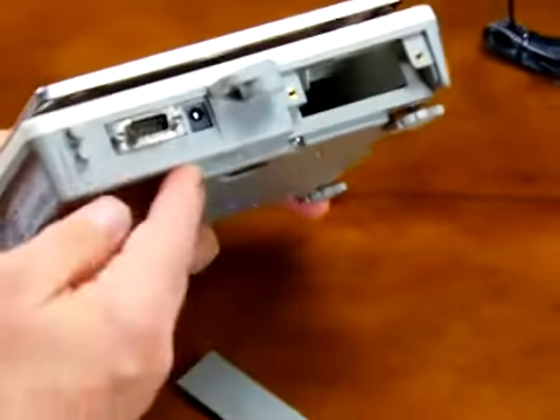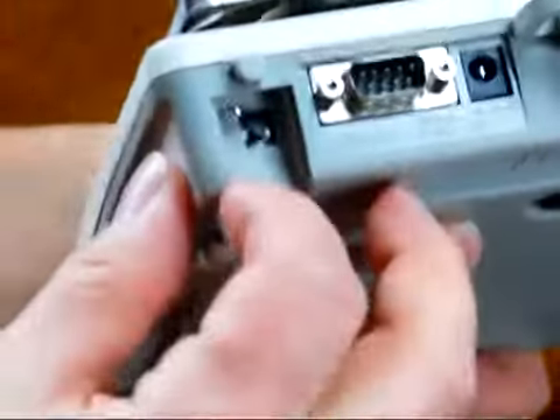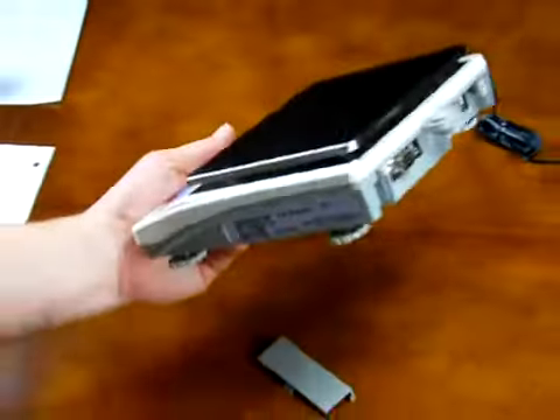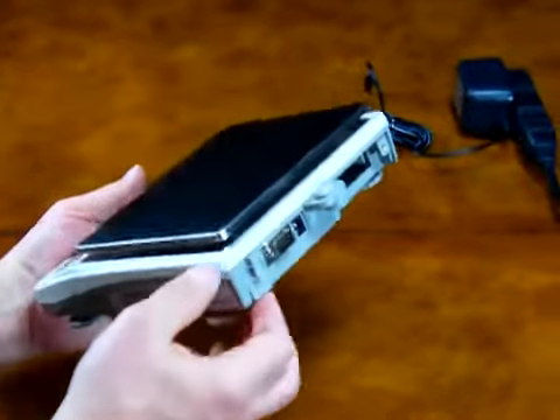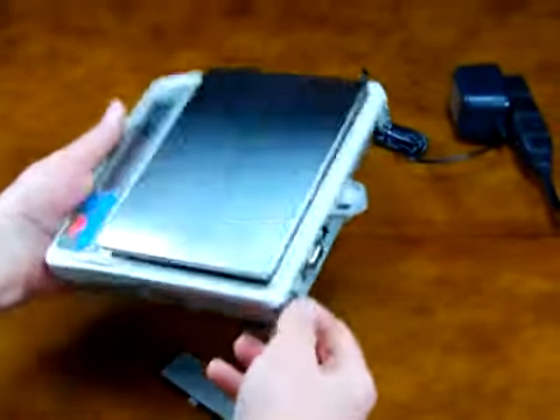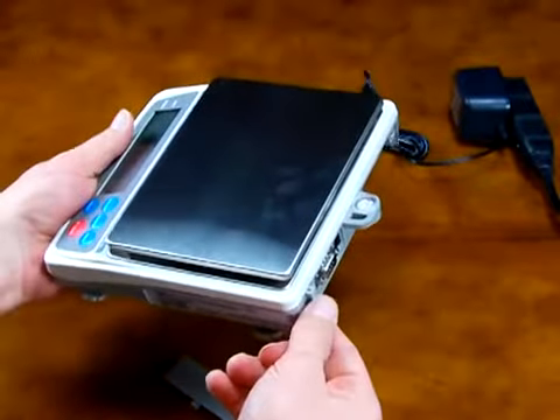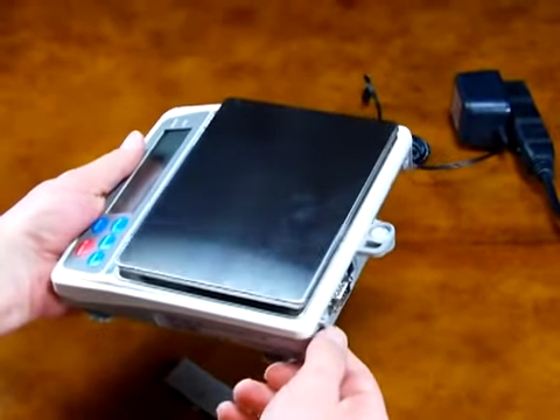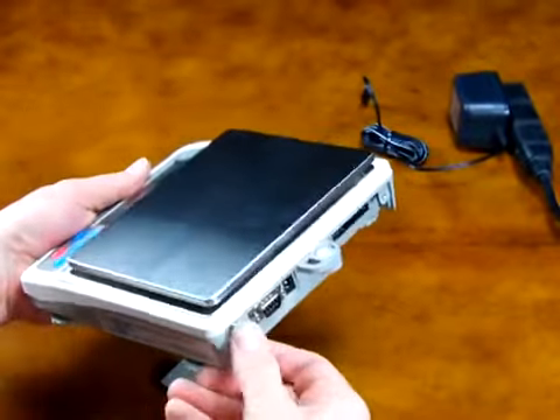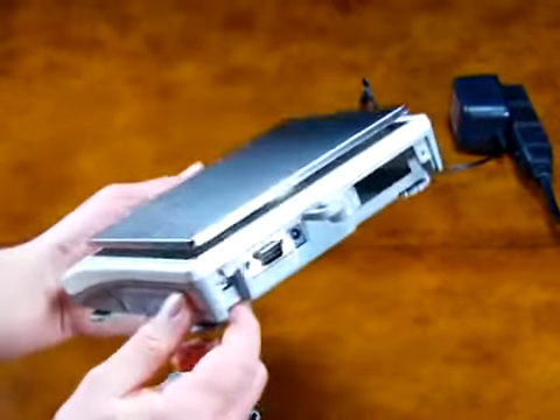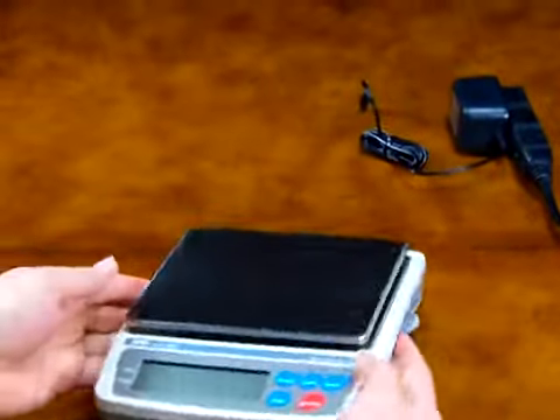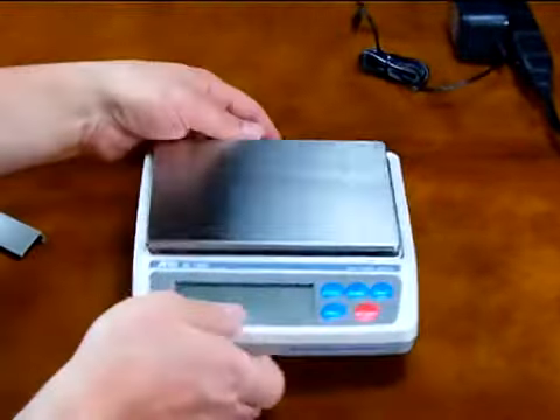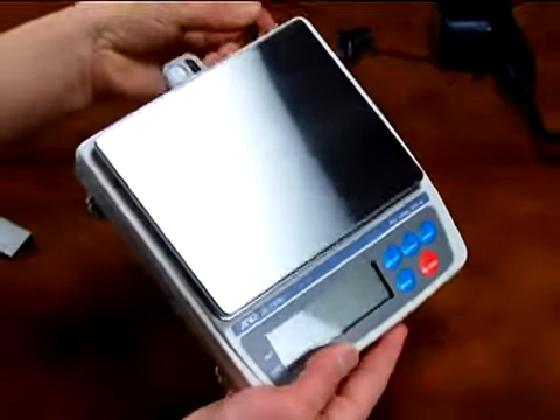The scale also has in the rear a port, or not a port, but a compartment. And this compartment is for the calibration. You would press this button to initiate the calibration. The scale has this cover here, and what Weights and Measures would do is they would put a cable through this hole so you are unable to calibrate the balance. That's one of the requirements for a legal for trade scale. So they just push this down. We're going to leave this off because we will perform a calibration. So the scale comes with the AC adapter, and we'll plug that in.